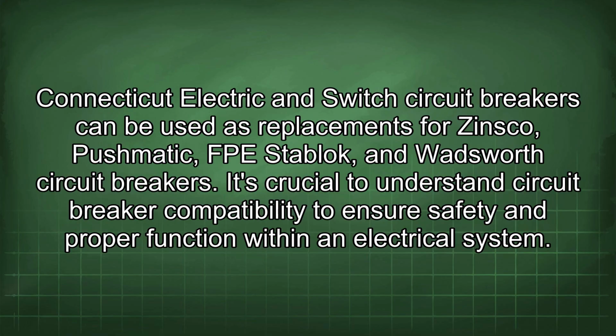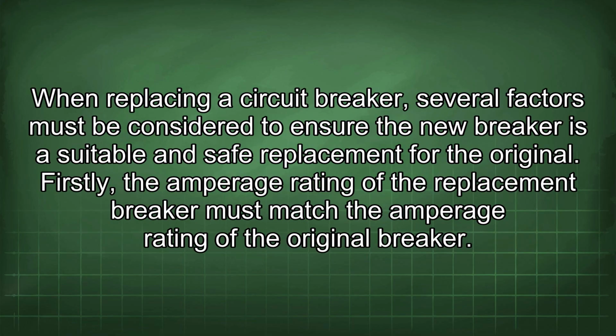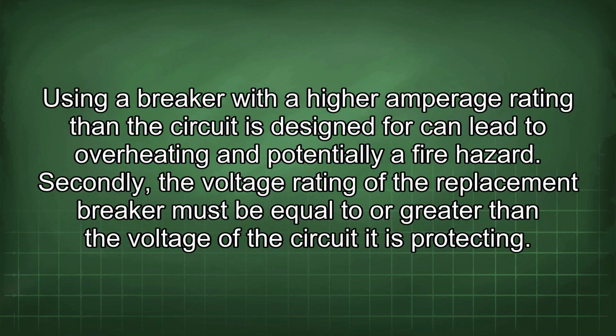It's crucial to understand circuit breaker compatibility to ensure safety and proper function within an electrical system. When replacing a circuit breaker, several factors must be considered to ensure the new breaker is a suitable and safe replacement for the original. Firstly, the amperage rating of the replacement breaker must match the amperage rating of the original breaker. Using a breaker with a higher amperage rating than the circuit is designed for can lead to overheating and potentially a fire hazard. Secondly, the voltage rating of the replacement breaker must be equal to or greater than the voltage of the circuit it is protecting.